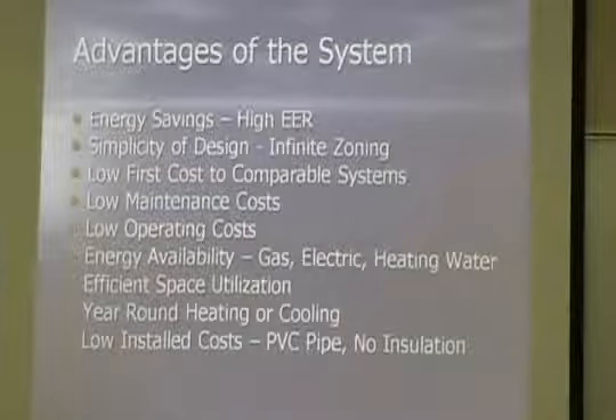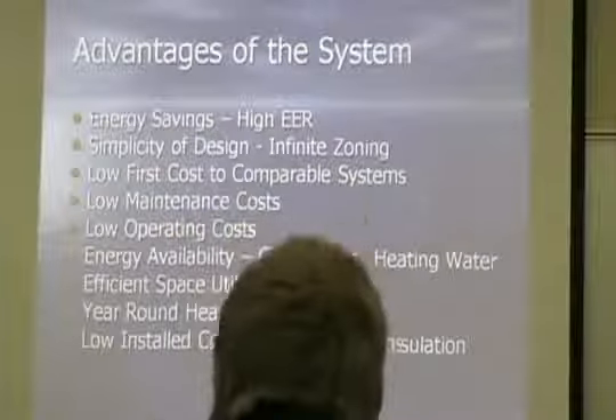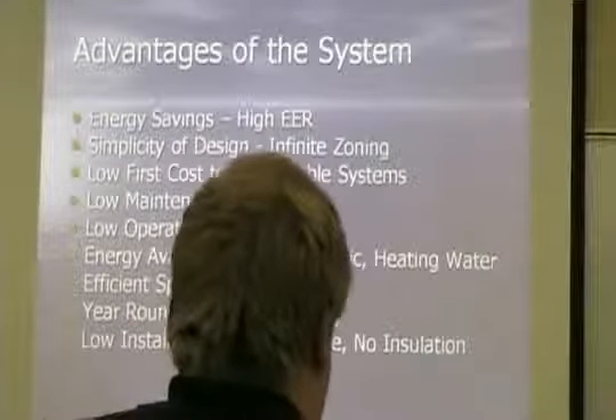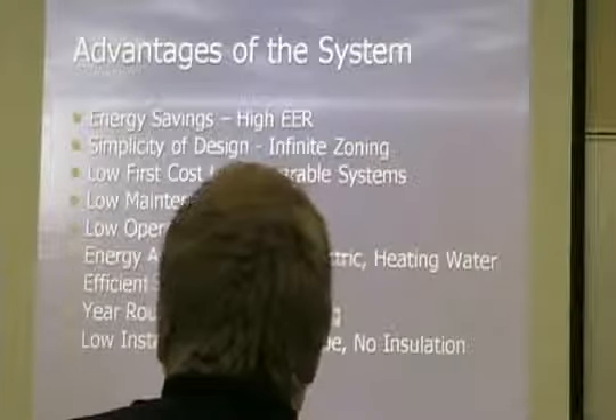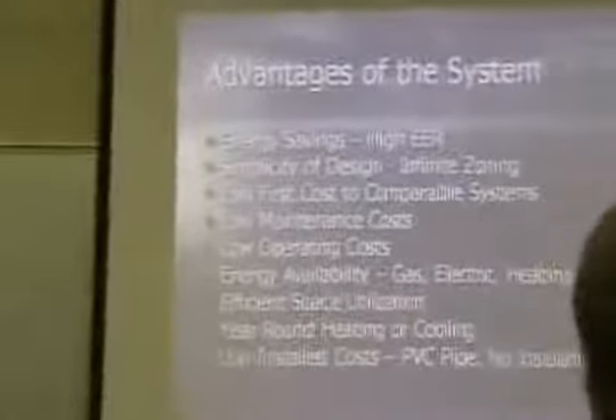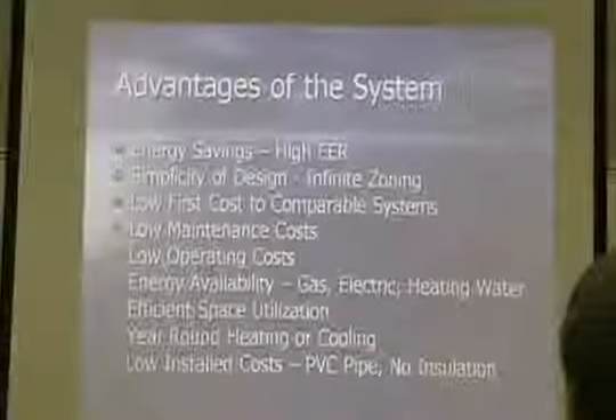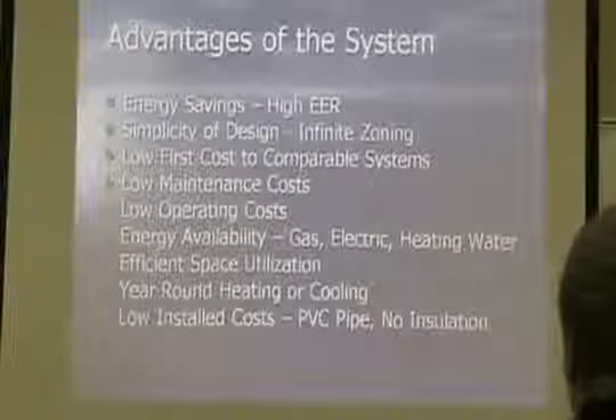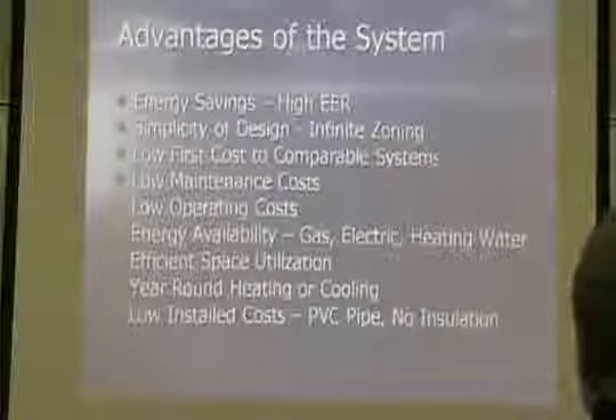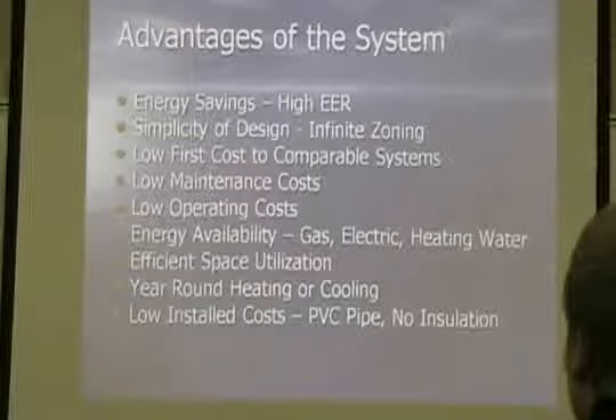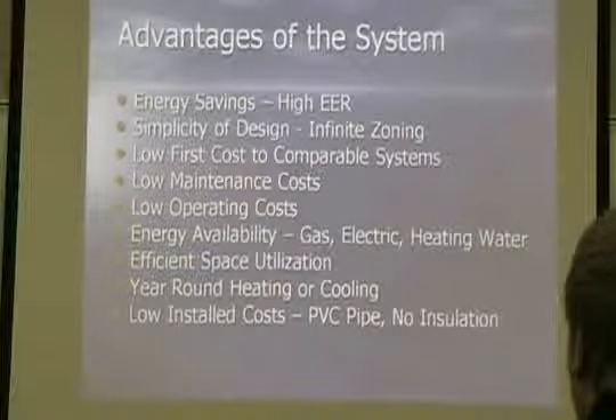EERs: most packaged air-cooled systems are in the 12 EER range, very high end. A water-cooled system, meaning I'm operating at condensing refrigerant temperatures of 105 to 110 versus 120 to 125 for an air-cooled system. So if I'm operating at a lower condensing temperature, my compressor lift is less, so my energy efficiency is naturally higher with a water-cooled unit versus an air-cooled unit. You have to consider that in a water-cooled system there are several auxiliaries that you have to pay for and operate, like pumps and cooling towers.